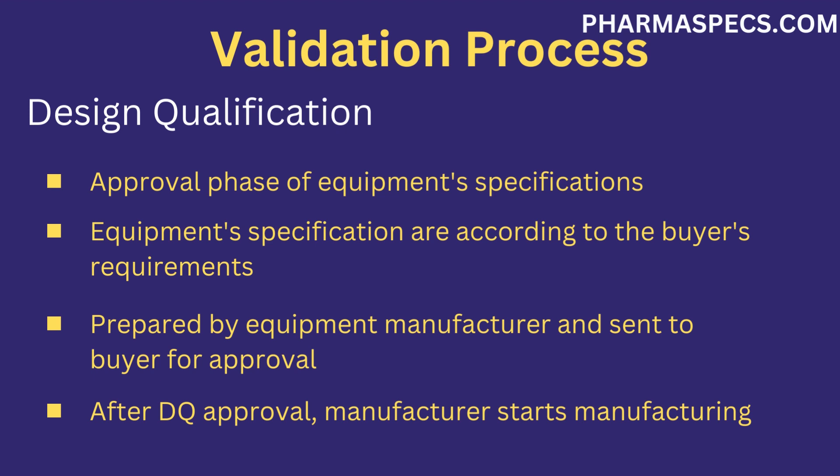In the design qualification stage, the specifications of equipment are checked to determine whether they are according to the buyer's requirements. The design qualification is prepared by the manufacturer and is sent to the buyer. The equipment buyer verifies it according to their needs and either approves it or does not approve it. When the DQ is approved by the buyer, the manufacturer starts manufacturing the equipment; otherwise, the manufacturer is bound to include all the required specifications in the design qualification phase.